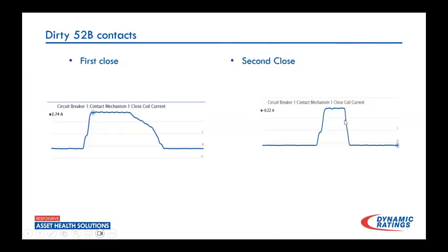But that's not to say that the next time, if it sits for a while, that these don't just sit completely shut the next time, or it takes 20 times as long. So this is the beginning of the problem, and really we need to get in there and start doing some maintenance at this point. The whole idea of the testing or online monitoring of it is we want to catch these failures before they happen.